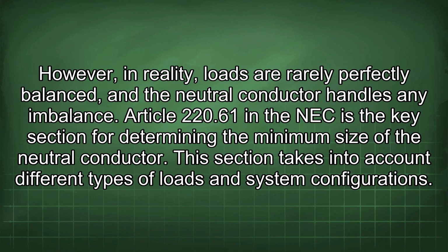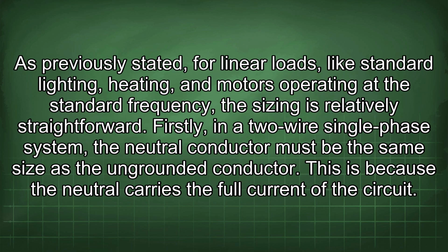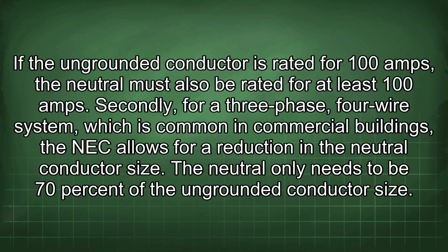Article 220.61 in the NEC is the key section for determining the minimum size of the neutral conductor. This section takes into account different types of loads and system configurations. As previously stated, for linear loads, like standard lighting, heating, and motors operating at the standard frequency, the sizing is relatively straightforward. Firstly, in a two-wire single-phase system, the neutral conductor must be the same size as the ungrounded conductor. This is because the neutral carries the full current of the circuit. If the ungrounded conductor is rated for 100 amps, the neutral must also be rated for at least 100 amps.